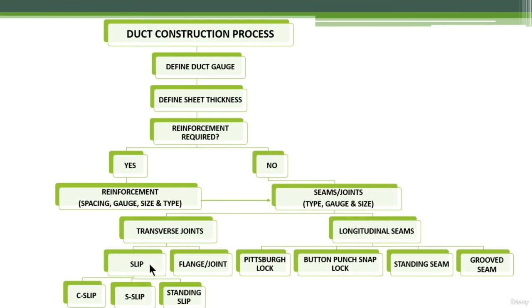The slip type consists of three further types: C-slip, S-slip, and standing slip — named based on their shape. The flange joint type uses flanges and gaskets to prevent leakage. These are the most commonly used transverse joints, and in approximately 70 to 80 percent of projects you will use either the C-slip or S-slip.